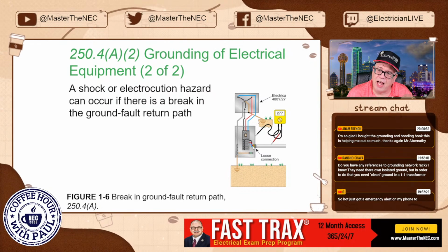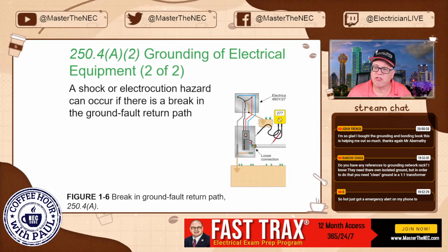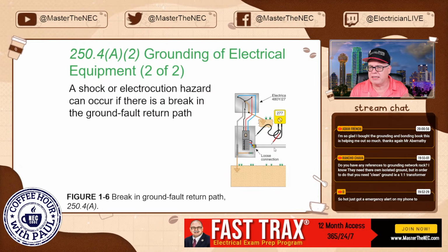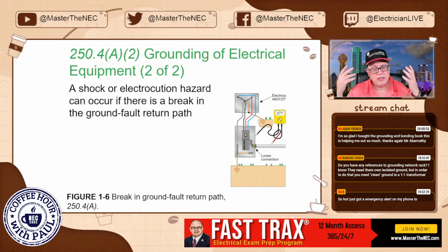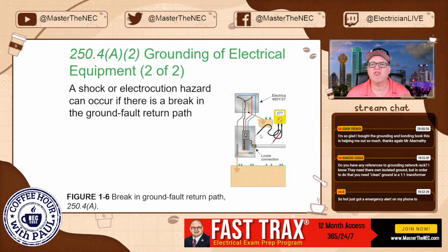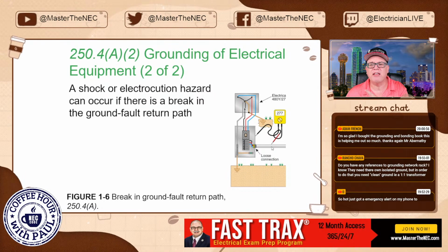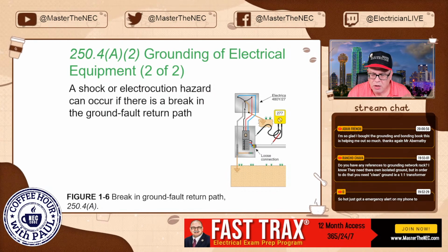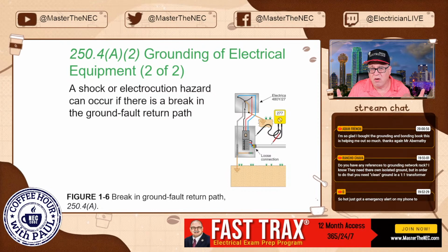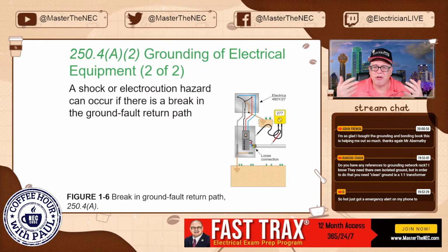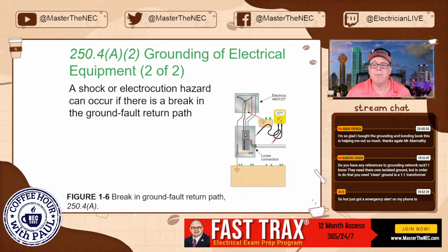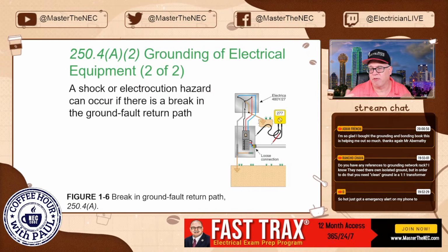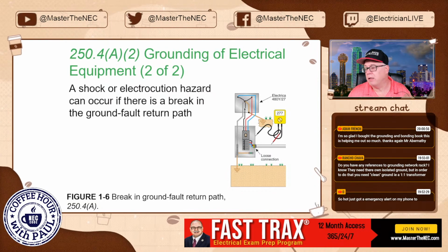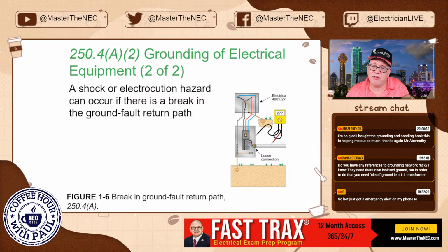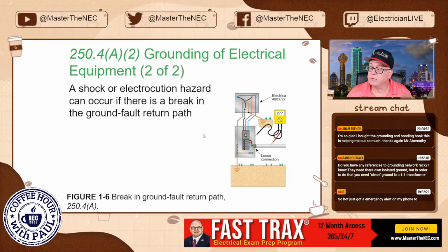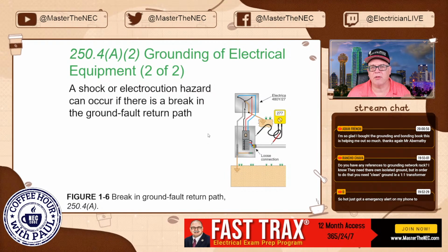Anyway, if this lock nut was done properly and adequately, then at the fault it would have cleared that overcurrent device very quickly. This is probably an inverse time breaker, so the more the current, the quicker the trip. Inversely proportional, so important. But because of that loose connection, this can sit here waiting. And that's the thing about electricity: when electricians install something and say it works, or do something that's a violation, electricity still tries to work. It's sitting there, sleeping, waiting for somebody to come in contact with it and complete that circuit. Then we've got a problem. So this could all just remain energized and it wouldn't have cleared the breaker. Scary thought. Make sure you make those connections.